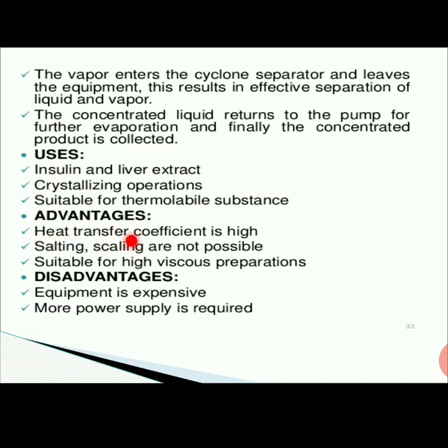Then what are the advantages? Here the heat transfer coefficient is high due to the rapid liquid movement caused by the pump. Then salting and scaling are not possible in forced circulation. This evaporator is suitable for thermolabile substances because of rapid evaporation, and it is suitable for highly viscous preparations because a pumping mechanism is used.